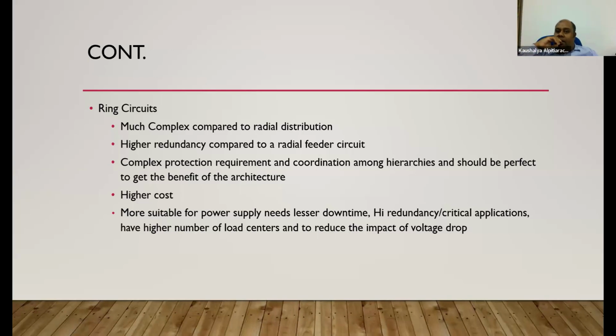Why is that? If you are going to feed radial circuits for many load centers, that means you are going to have an extensively bigger secondary distribution panel, which will occupy a much larger footprint. So you can reduce the footprint by having a ring circuit and distributing load centers among the ring circuit.